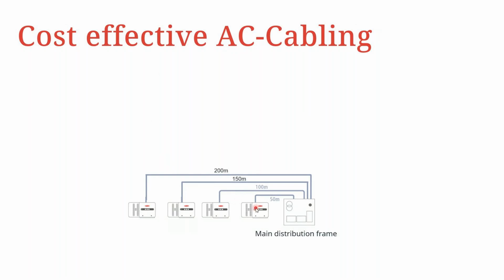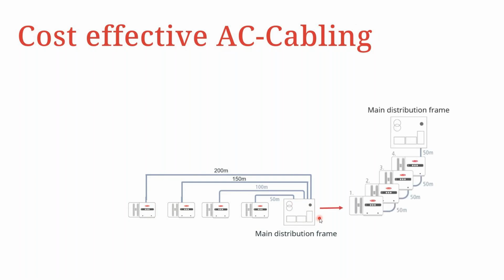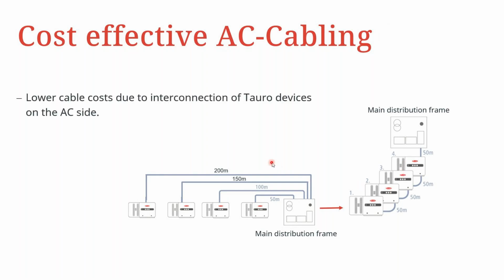So basically, if you have a collection of inverters that are installed, say, for example, in a decentralized system design, you would have them at various distances from the main AC distribution frame. That means that you'd have to run separate and consecutive AC cables from each inverter respectively to the main distribution frame. Or you can have something like this. You can have the inverters AC daisy chained and connected singularly to the main distribution frame. Now that's special.